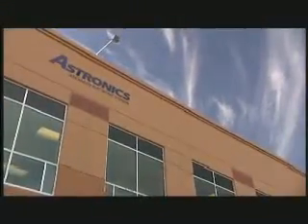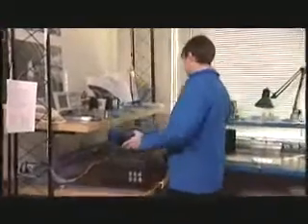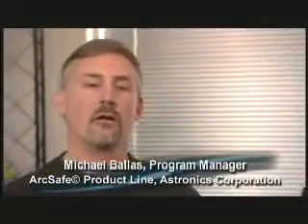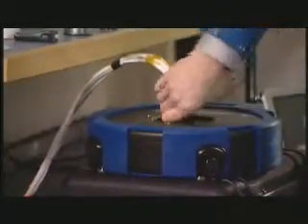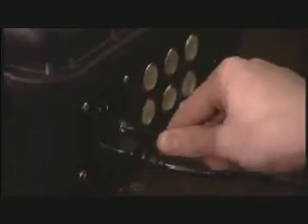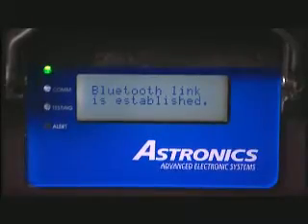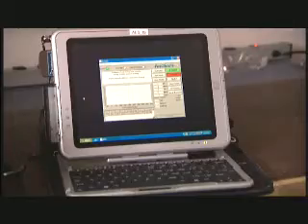We're proud to announce that we have licensed this patented technique to Astronics, which is a former General Dynamics division. They have commercialized the package into something about the size of a suitcase. I'm Michael Ballas with Astronics, and I'm the program manager for our ArcSafe product line. We've been under contract with the FAA for the last five years to develop a state-of-the-art technology for finding faults in aircraft wiring. We've acquired technology from Sandia Labs, referred to as pulse-arrested spark discharge, and we're in our initial production release of the AS-1216 arc fault detection system.